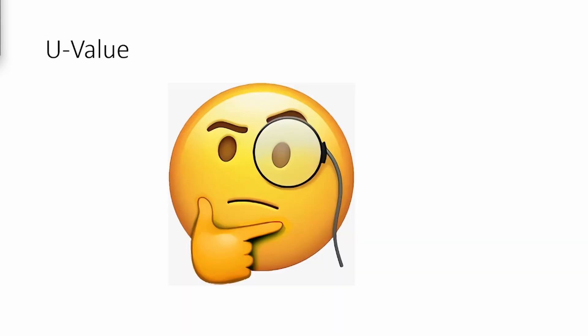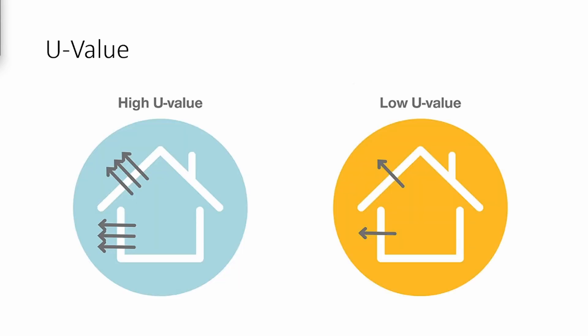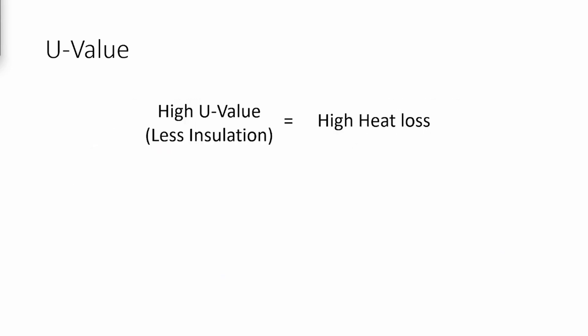One thing that is discussed often when it comes to comparing insulation materials are the U-values. The U-value measures insulation effectiveness, quantifying heat that passes through a material per unit area for a given temperature difference. Higher U-value has worse insulation properties, while lower U-values indicate better insulation properties.